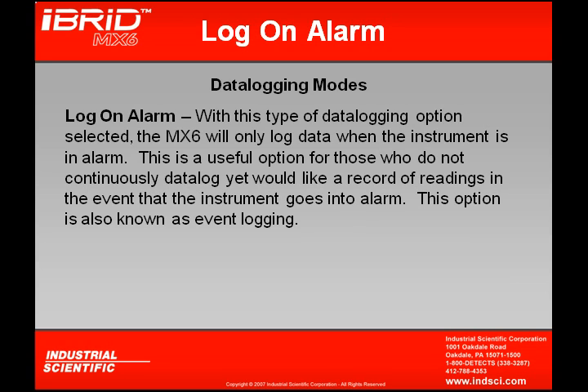Log on Alarm is another option available for my data logger. For those who don't want to continuously data log, Log on Alarm is a great option. With this type of data log option selected, the MX-6 will only log data when the instrument is in alarm. So rather than downloading hundreds of hours of all zeros, the only thing I'm downloading are actual alarm conditions. This is a very useful option for those who would like a record of a reading in the event that the instrument goes into alarm. This option we also call Event Logging.